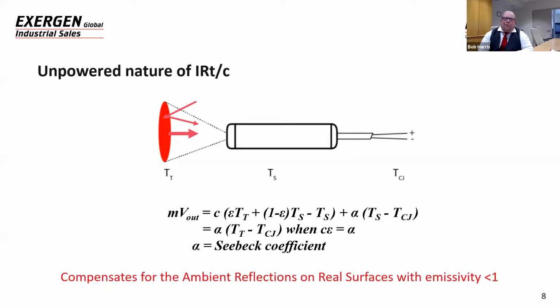So what we do is we calibrate on gray body targets, and we calibrate in ambient blocks that will compensate for the ambient reflections on real surfaces where the emissivity is less than 1. In other words, the gray body targets we use here are 0.9. So when we calibrate the sensor, we're calibrating for the effects of the emissivity as well, so that it matches the millivolt signal out of a thermocouple at that temperature, with the effects of the ambient reflections and the ambient temperature.